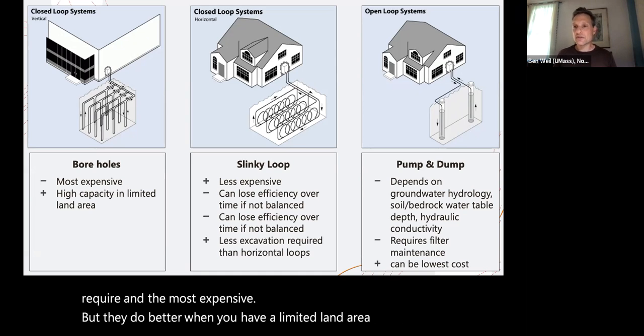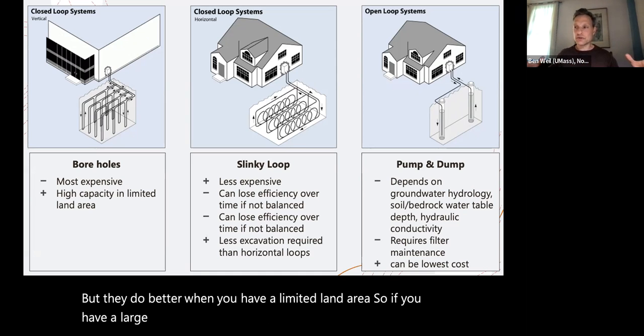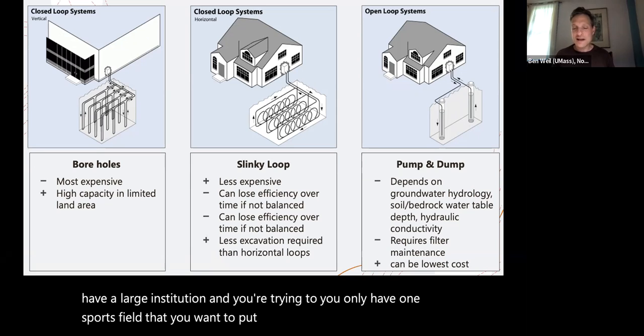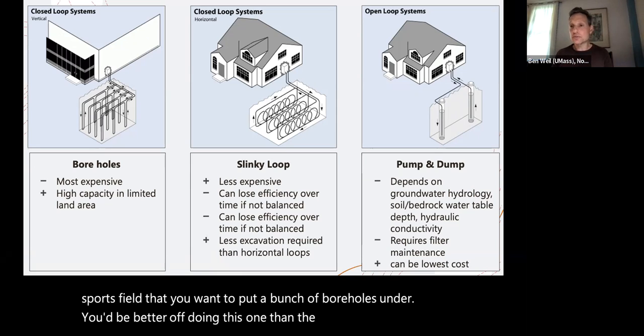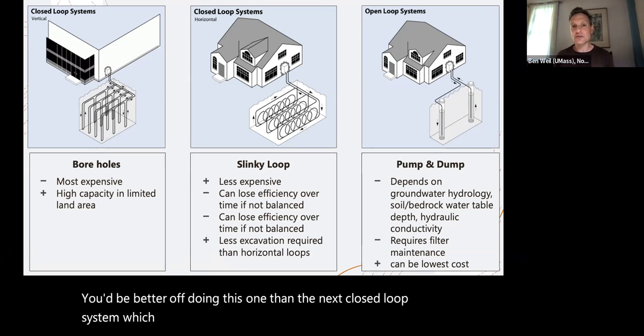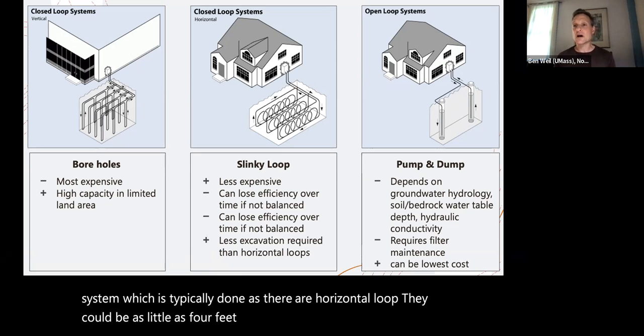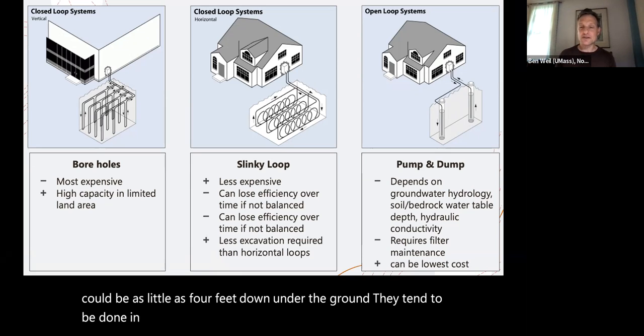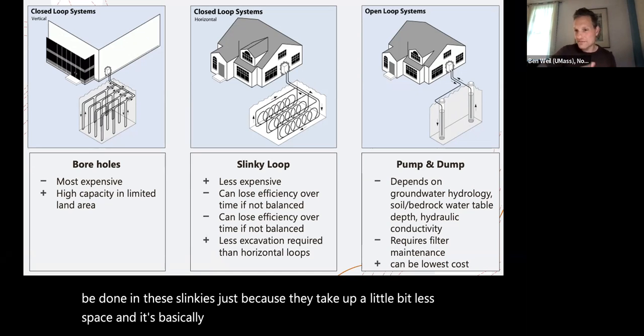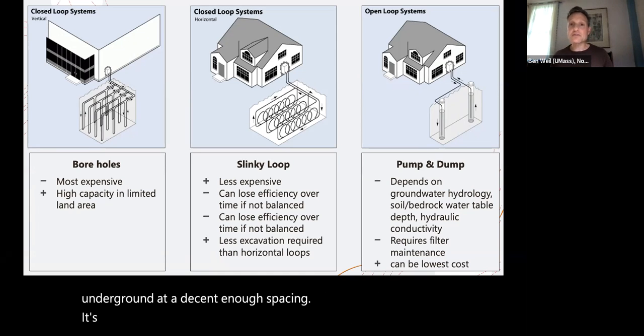So if you have a large institution and you only have one sports field that you want to put a bunch of boreholes under, you'd be better off doing this one than the next closed loop system, which is typically done as a horizontal loop. They could be as little as 4 feet down under the ground. They tend to be done in these slinkies just because they take up a little bit less space, and it's basically this flexible pipe that's just set underground at a decent enough spacing. It's considerably less expensive, particularly if you're already doing a fair amount of excavation.